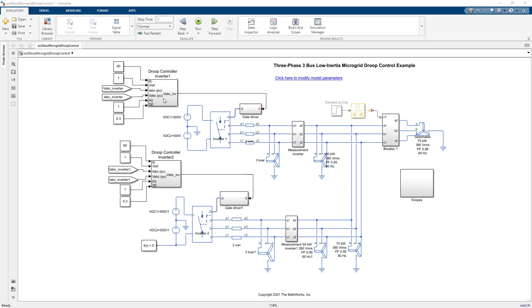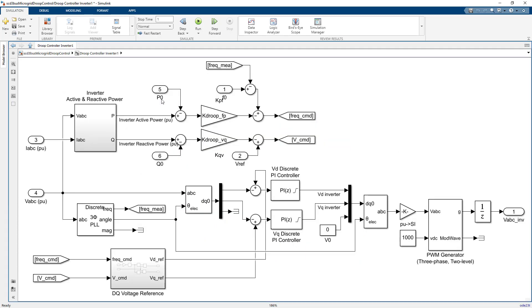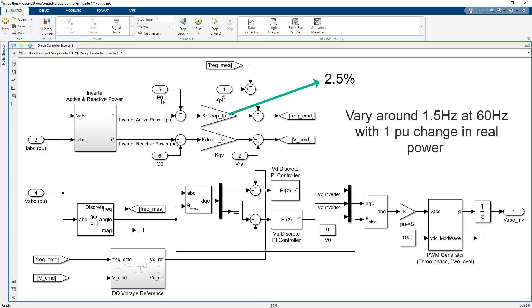In this droop controller design, the active power frequency droop coefficient is set to 2.5 percent, meaning that microgrid frequency is allowed to vary 1.5 hertz around 60 hertz with one per unit change of real power injected from the inverter.